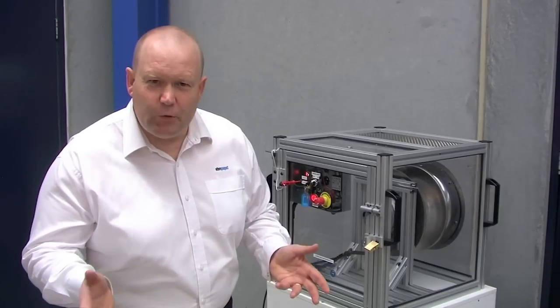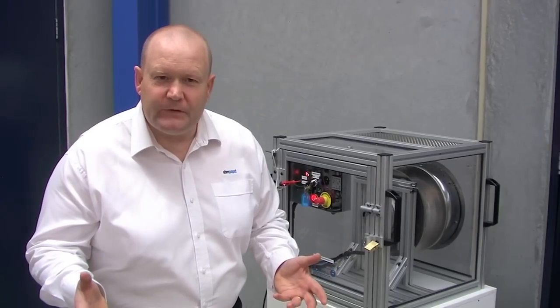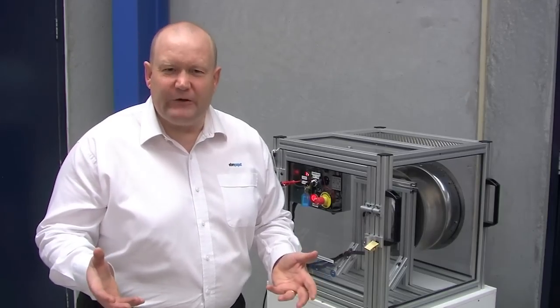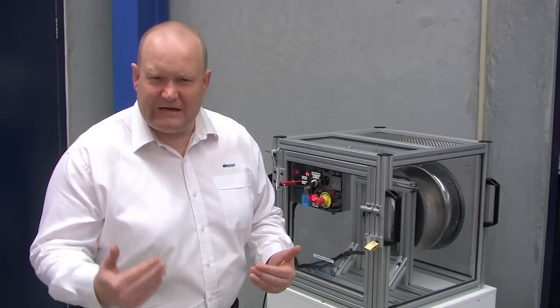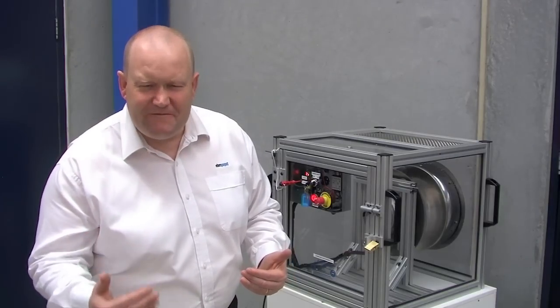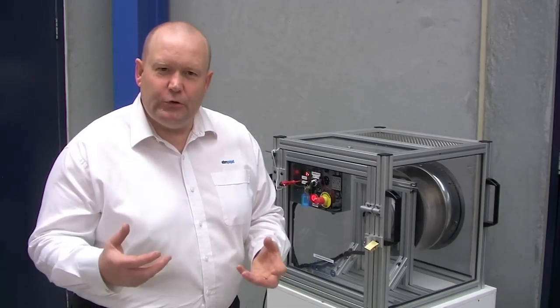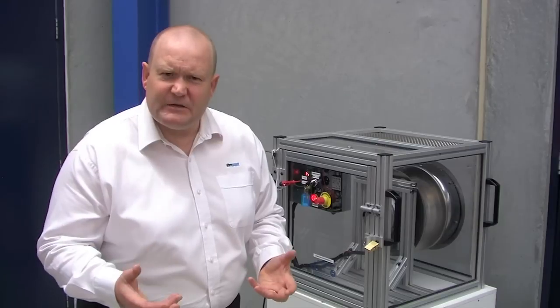So here we are with a smaller EC plug fan to show the benefits of speed control. First of all, with EC plug fans you can apply the fan laws, which means if you speed control a product from 100% speed down to 80% speed, you get 50% power savings.